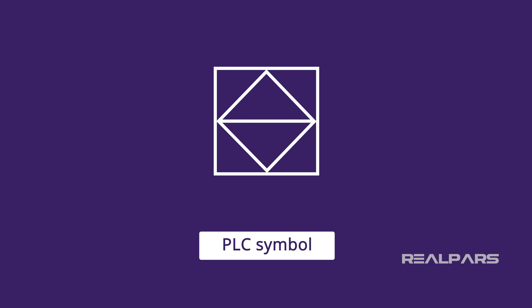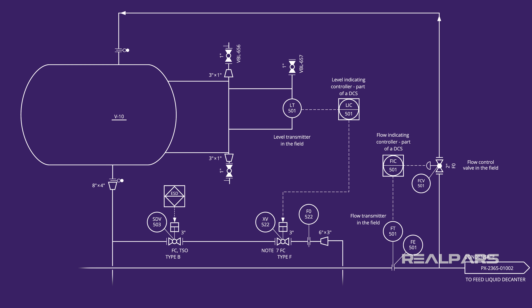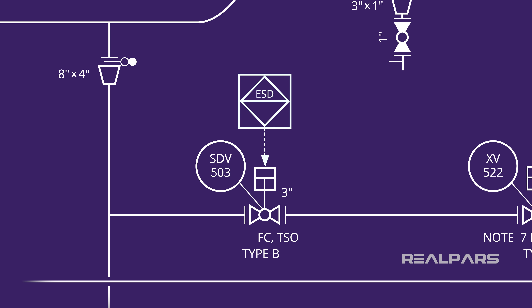PLC symbols don't show up on P&IDs nearly as often as DCS symbols, but when they do show up, they are drawn as a diamond inside a box. All you have to know is that the symbol represents a software instruction to perform some function in the plant. For example, the PLC symbol on our P&ID indicates that the SDV503 valve is operated by the emergency shutdown software instruction written in the PLC program.